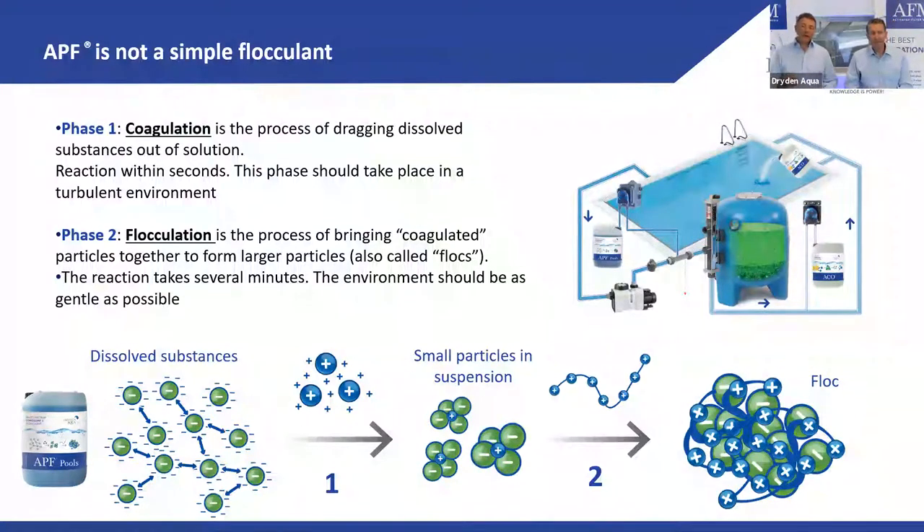Here you see the dissolved substances — for example phosphates — which are negatively charged and repel each other, staying in solution. When you add a positively charged coagulant — an electrolyte — you neutralize the charge and destabilize them, bringing them together into very small colloids. Then flocculation uses long-chain molecules that act like a fishing net, gathering these small particles into a large floc which is easy to remove.